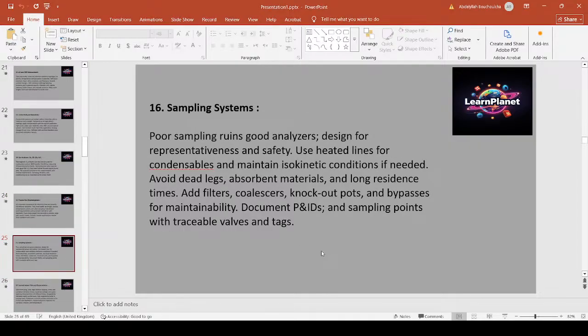Sampling systems. Poor sampling ruins good analyzers; design for representativeness and safety. Use heated lines for condensables and maintain isokinetic conditions if needed. Avoid dead legs and absorbent materials, and long residence times. Add filters, coalescers, knockout pots, and bypasses for maintainability. Document P&IDs and sampling points with traceable valves and tags.